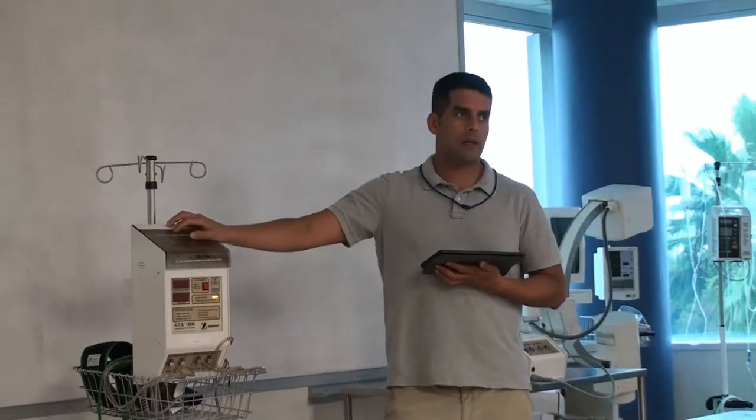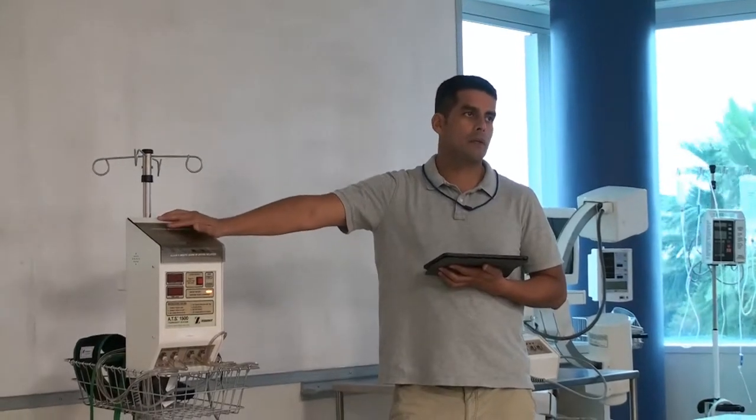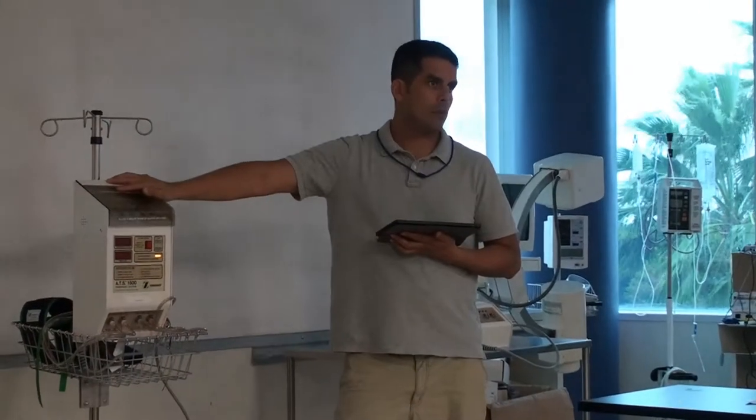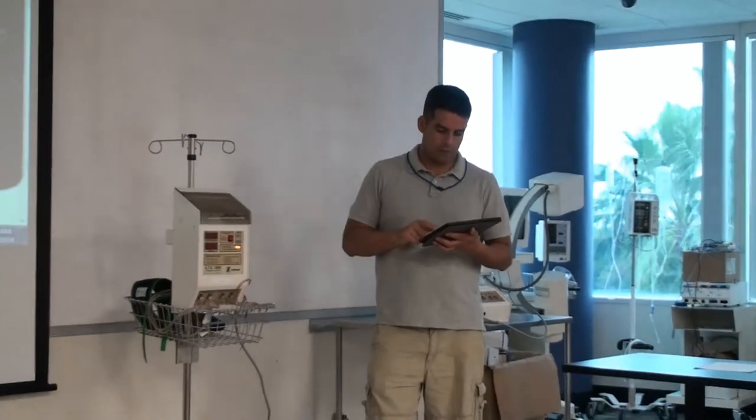And when you calibrate, the manufacturer suggests like a plus minus six millimeters mercury during the calibration process, just to have more accuracy during your procedure or your surgical procedures.